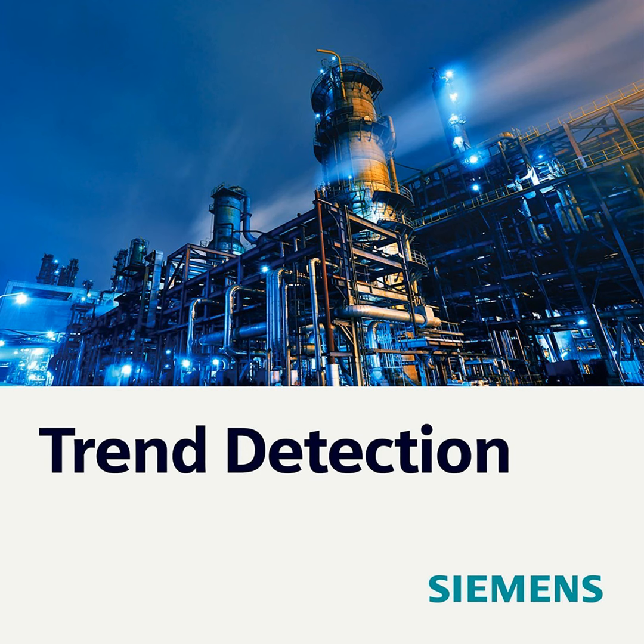And then the story goes further. So when you know, okay, there is an anomaly in my system, I have to find out what is causing that. You have something we call an explainer. It gives you an indicator which value is causing this anomaly. So is it an anomalous torque or an anomalous speed value? And with this knowledge, you can go and find out what caused this behavior in the machine.